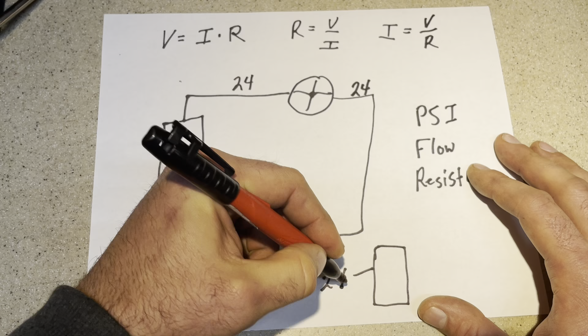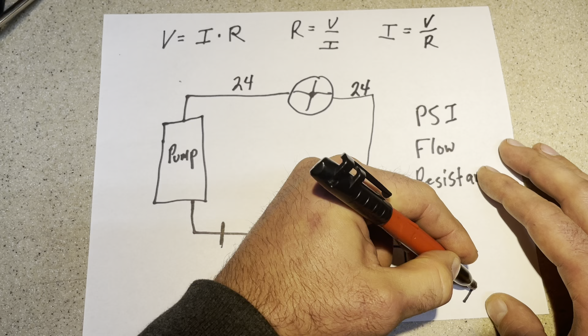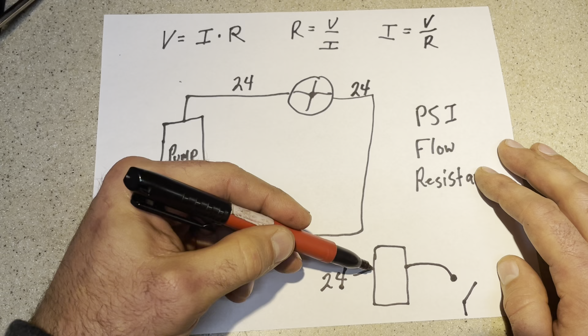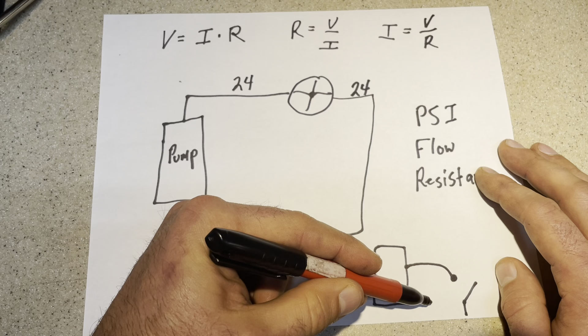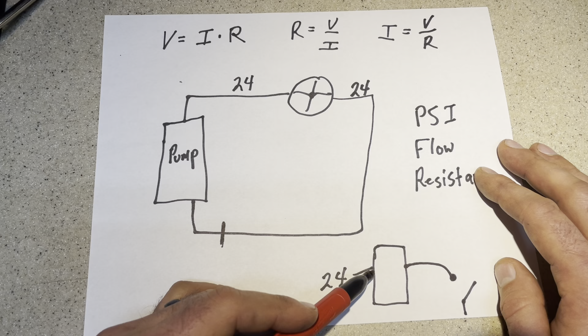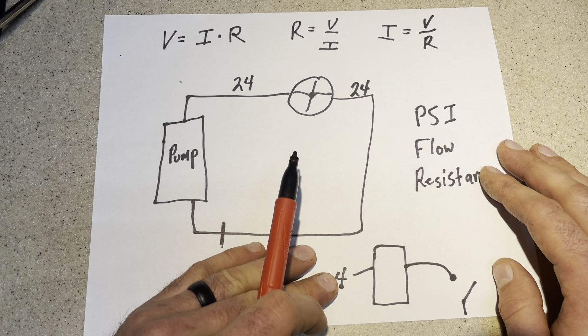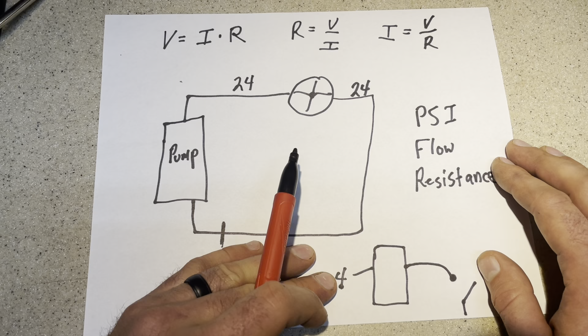And this is why on a contactor that's off, let's say I have 24 volts going to the contactor, but I have a common over here that's switched off. If I'm measuring 24 volts to ground, what am I going to see on this side? 24 volts to ground. And if I measure here, what am I going to see? 0 volts, because I've got 24 on this side and 24 on that side. So a meter doesn't care whether there's voltage somewhere or not. I can have 24 volts here but still measure 0. Why? Because all the meter is telling you is the potential difference between one point and another point. If there's no potential difference, then electrons don't want to flow, and your voltage then is 0.